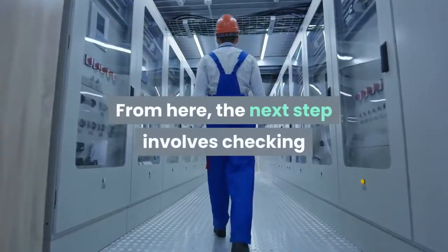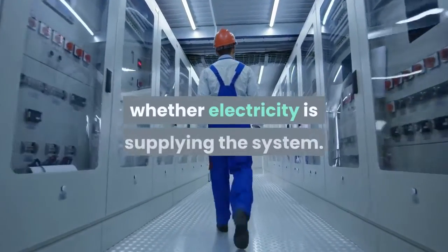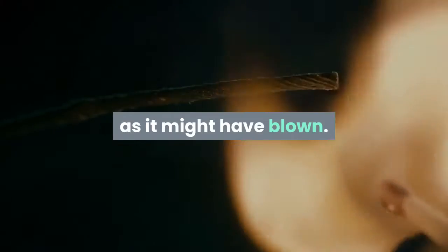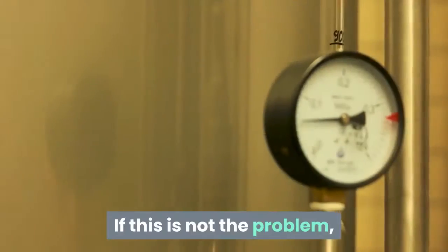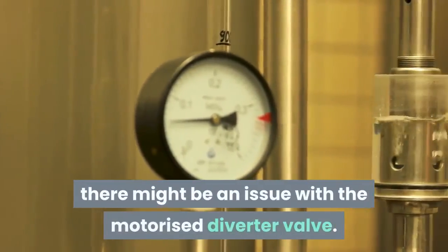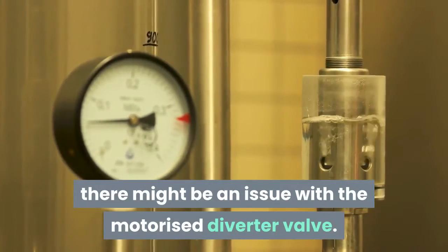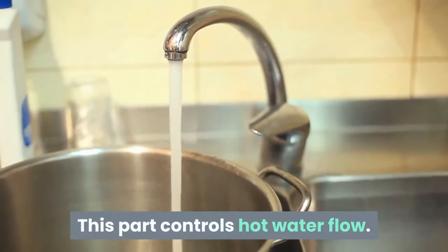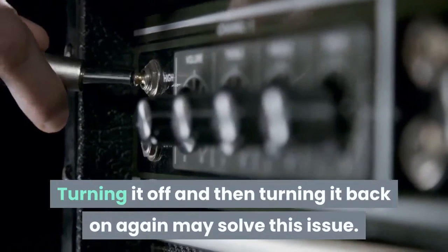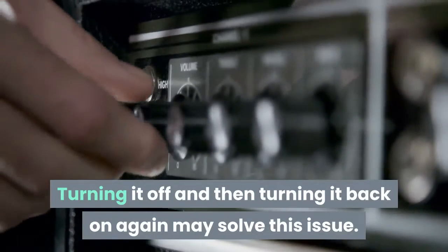From here, the next step involves checking whether electricity is supplying the system. This also includes checking on the heating fuse, as it might have blown. If this is not the problem, there might be an issue with the motorized diverter valve. This part controls hot water flow. Turning it off and then turning it back on again may solve this issue.